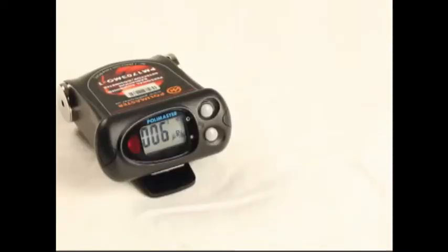The meter is preset with two alarms, a Low Alarm and a High Alarm. These alarms are set at designated levels to notify the user to the presence and rate of radiation. Low alarm signifies radiation reading significantly above the background, but still no immediate hazard.